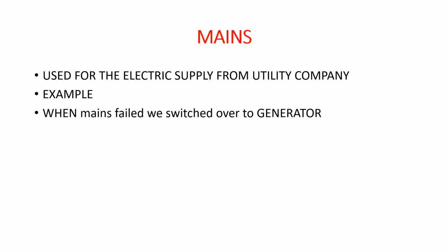So mains is used for the electric supply from the utility company. For example, when mains failed, we switched over to the generator. The supply from the generator is not known as mains, although it comes to your main control board, panel board, or distribution board - we will have a separate video on boards. But whenever somebody says mains failed, it always means the electric supply from the utility company, like Hydro One, failed and is no longer available, so we switch to a generator, diesel generator, UPS, or solar panel, whatever. So mains means the electric supply from the utility company.